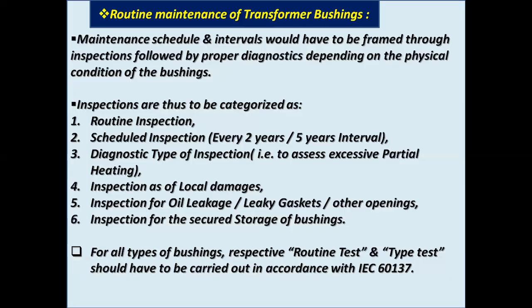Diagnostic type of inspection, to assess excessive partial heating. Number 4, inspection for local damages. Number 5, inspection for oil leakage or leaky gaskets and other openings. Number 6, inspection for the secured storage of bushings. For all types of bushings, the respective routine test and type test should be carried out in accordance with IEC 60137.